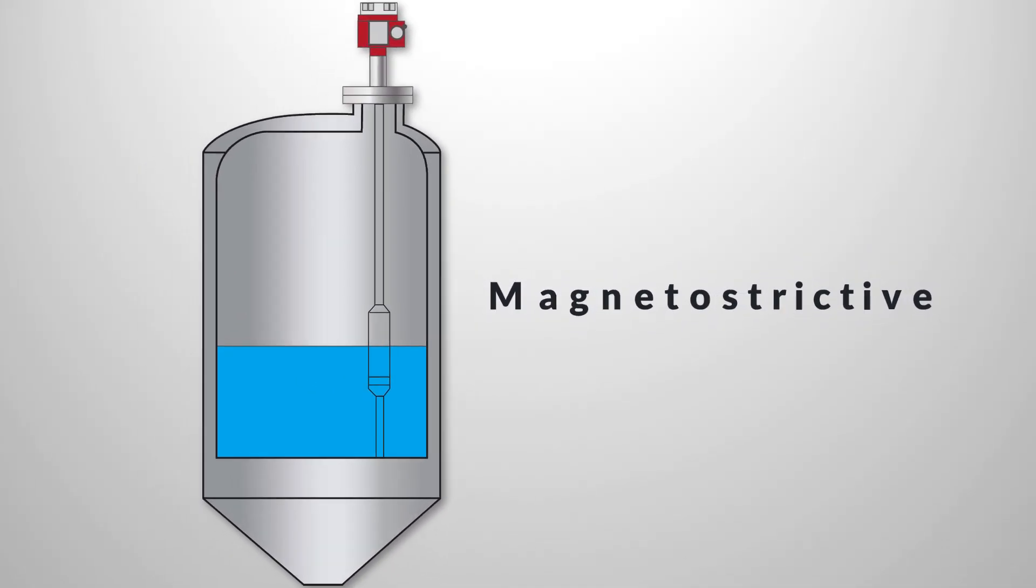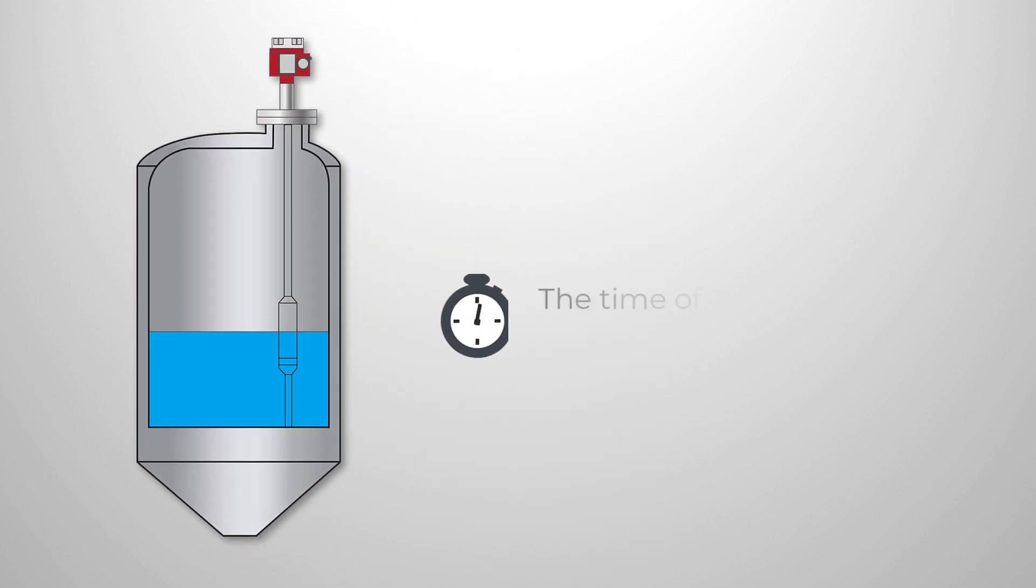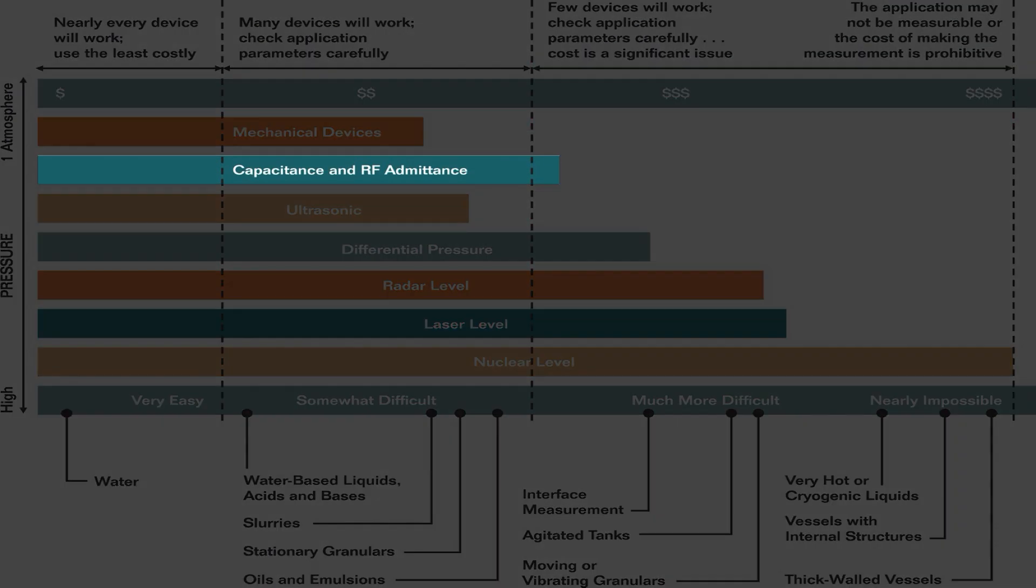Magnetostrictive level gauges use a float containing a permanent magnet that moves freely up and down a magnetostrictive waveguide. A low-current interrogation pulse travels down the waveguide and when it reaches the float, a torsional twist and reflection are created. The time of reflection indicates the float position and level.